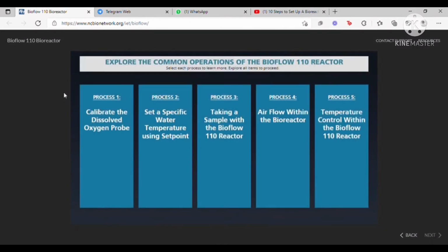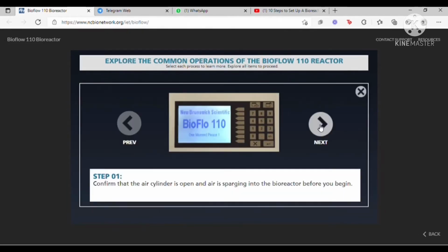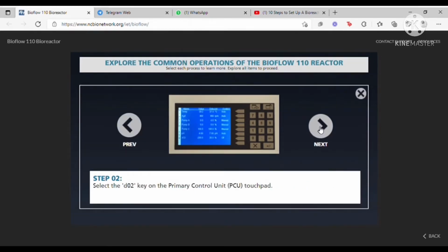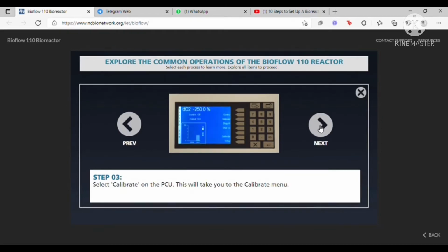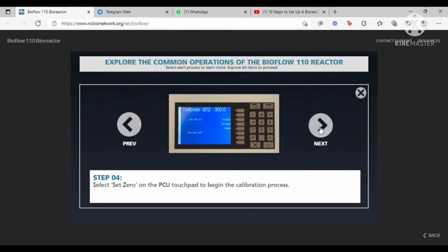So now we will explore the common operations of the Bioflow reactor. The first one we will be looking at is process 1, which is to calibrate the dissolved oxygen probe. Step 1 would be to confirm that the air cylinder is open and air is sparging into the bioreactor before we begin. Next, step 2 would be to select the DO2 key on the primary control unit, also known as the PCU touchpad. Next would be step 3, which is to select calibrate on the PCU. This will take us to the calibrate menu.